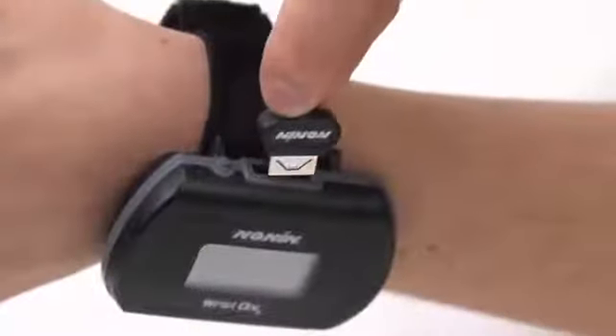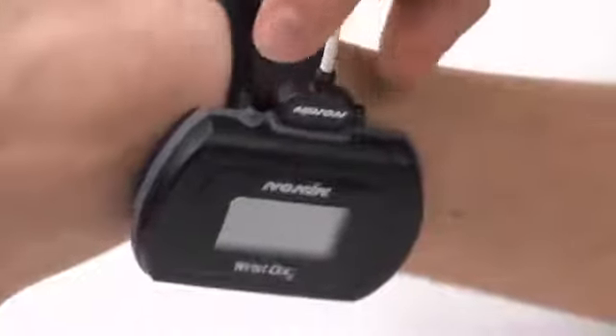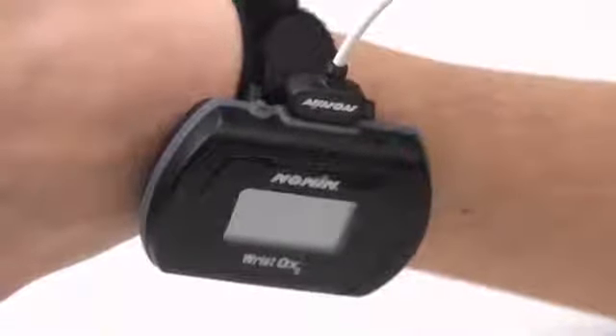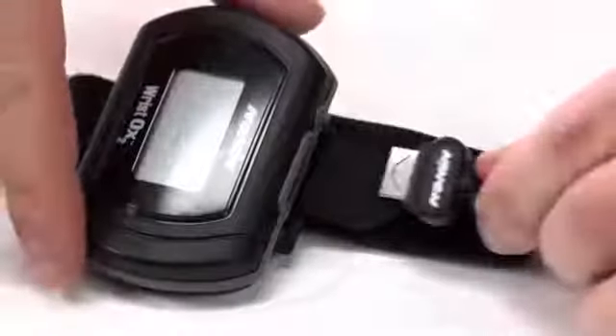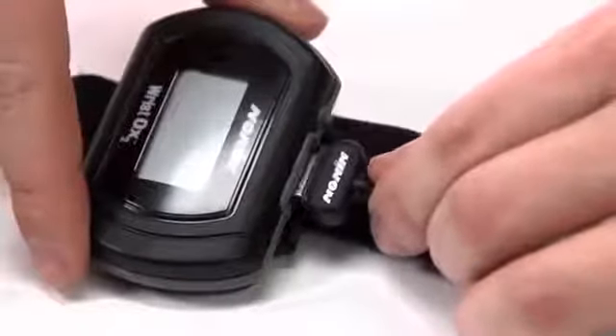Connect the sensor to the WristOx2 pulse oximeter by inserting the plug with the NONIN logo visible at the top of the sensor port, as shown here. The connector should firmly seat in the connector port on the oximeter.